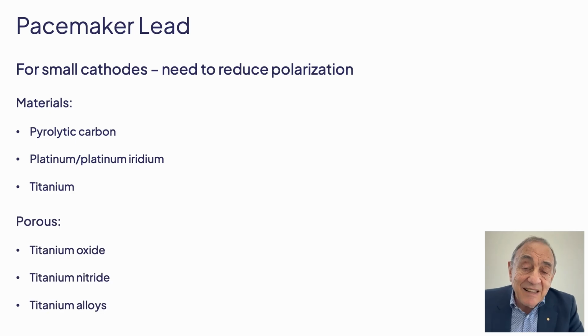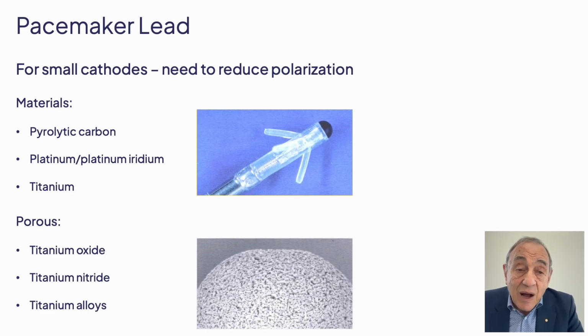But what is particularly valuable is that we have now created porous leads with titanium overlay, and in this way created a very small gross surface area to the lead, but the pores result in a massive increase in the actual size of the cathode, and in this way it reduces polarization. Despite these marked advances, we still had problems with high threshold exit block.